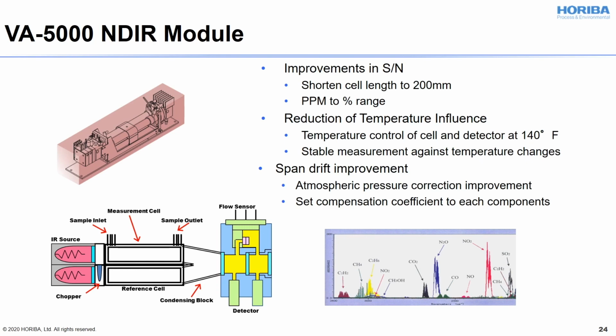The VA-5000 uses the NDIR measurement method. NDIR covers from the ppm level to percentage. We keep the measurement cell at 140 degrees F. Keeping the cell warm improves the measurement, because ambient temperature change is one of the biggest factors in fluctuation of the measurement value. Also, it helps to keep the sample gas dry and the moisture away. Moisture may capture the sulfur compounds, which damages the cell or causes drift. NDIR cells have atmospheric pressure correction as standard, and it always works to compensate each component.